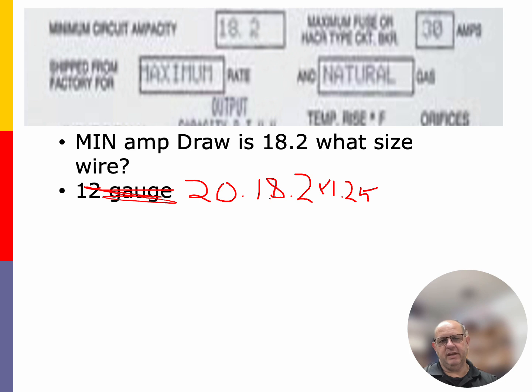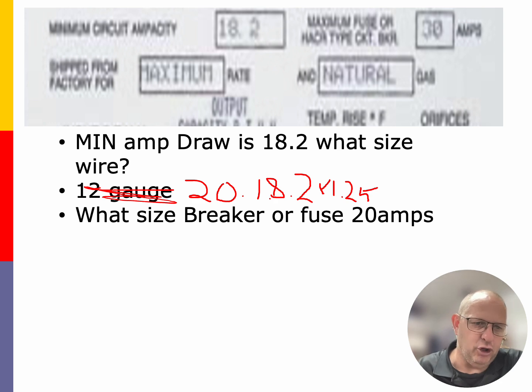Given the fact that we also are given a maximum size breaker on this, I tend, as an HVAC technician, to always go to the maximum amp draw of that particular unit and the maximum fuse for that particular unit, and then install the correct breaker and the correct wire for the maximum fuse or the maximum HACR type of circuit breaker for that particular unit.